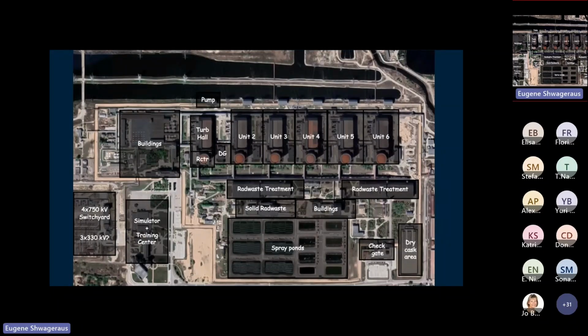Now, on the site, what we see here is 6 units. The containment buildings are cylindrical - you see them here. The rectangles attached right next to those are turbine halls, so 6 turbine halls. Each unit has 3 diesel generators that provide emergency pumping power, so in case of loss of off-site power to the plant, these diesel generators kick in and provide all necessary loads, most importantly pumping power for cooling.